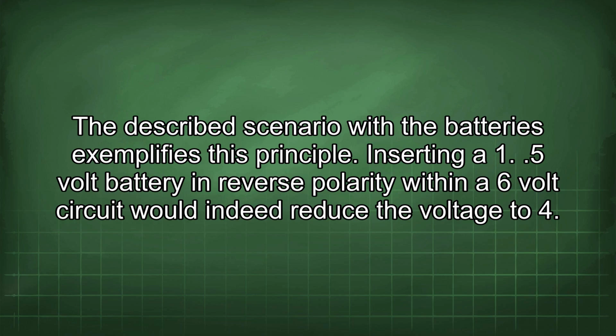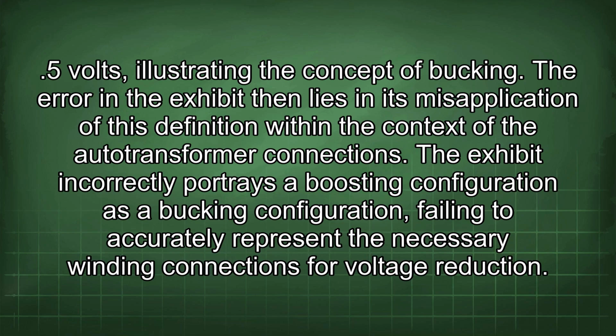Inserting a 1.5-volt battery in reverse polarity within a 6-volt circuit would indeed reduce the voltage to 4.5 volts, illustrating the concept of bucking. The error in the exhibit then lies in its misapplication of this definition within the context of the autotransformer connections. The exhibit incorrectly portrays a boosting configuration as a bucking configuration, failing to accurately represent the necessary winding connections for voltage reduction.